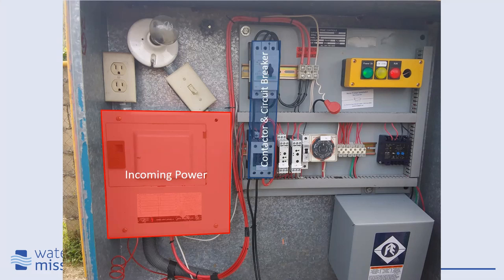Now you see that I'm also including this component above the contactor. That's because that is a circuit breaker. And it's a very standard assembly to have your circuit breaker directly above, directly before your contactor. Even if you have a circuit breaker for your main system, right before your contactor, you should have its own circuit breaker.